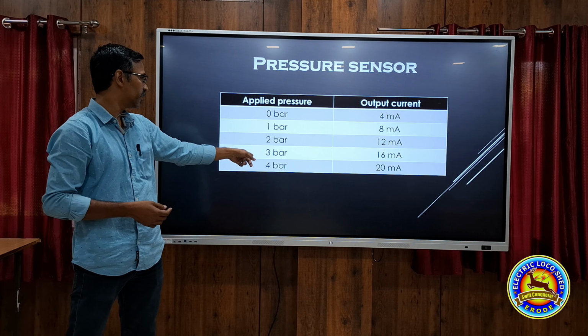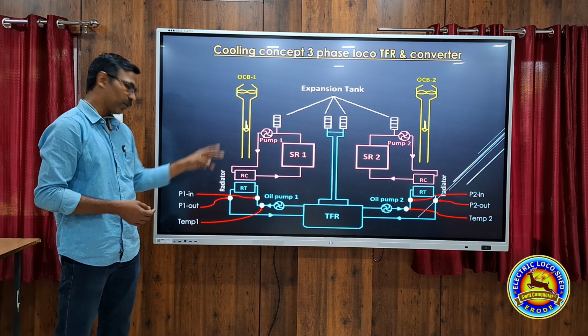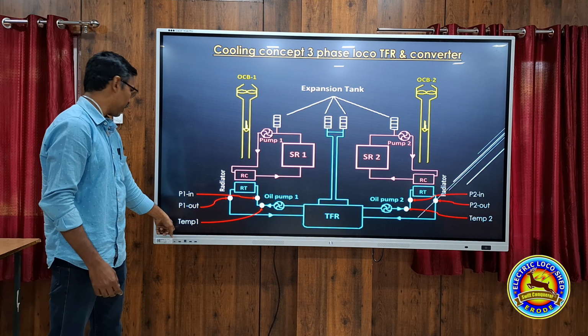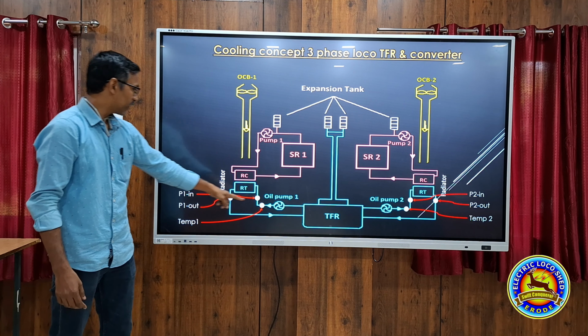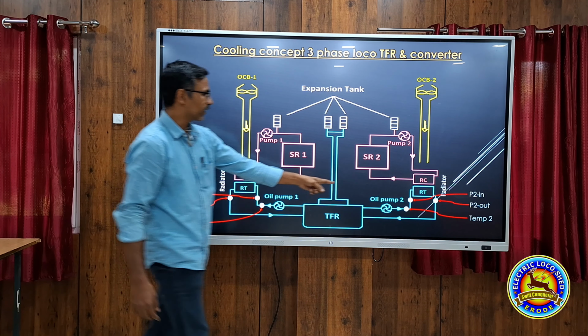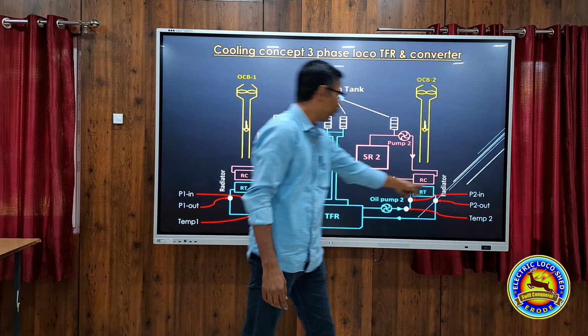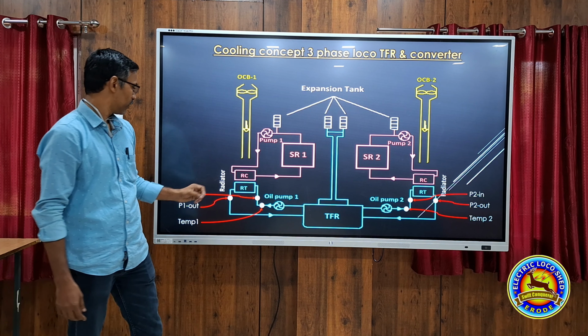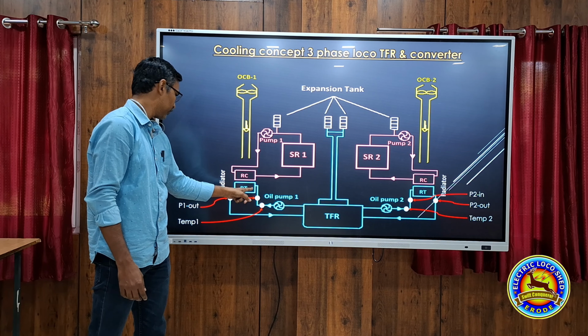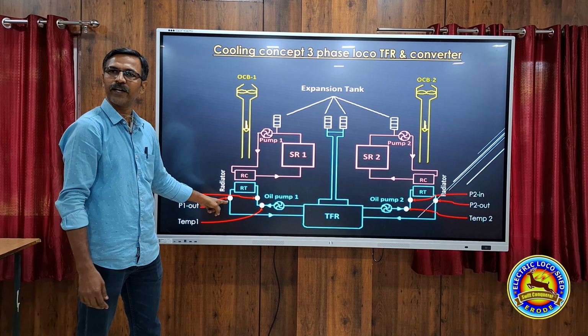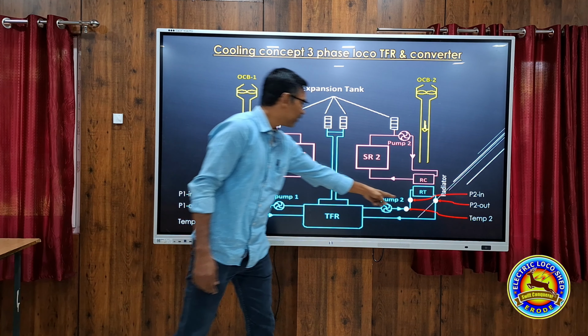This is the cooling concept of the three-phase loco, transformer and traction converter. These are the locations where our sensors are connected. In a three-phase loco, for the oil cooling circuit, there are two temperature sensors, temp 1 and temp 2. One is connected at the oil pump 1 circuit, another at the oil pump 2 circuit. And there are 4 pressure sensors. One is connected to the input of radiator 1 and one at the output of radiator 1. Similarly, there is one at the input and one at the output of radiator 2.